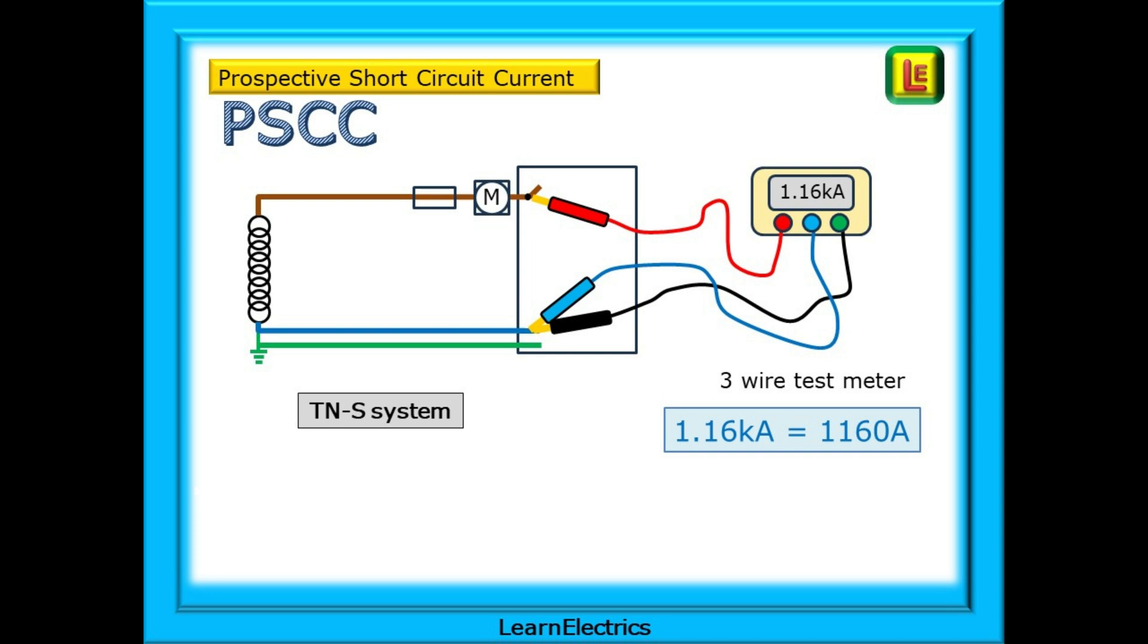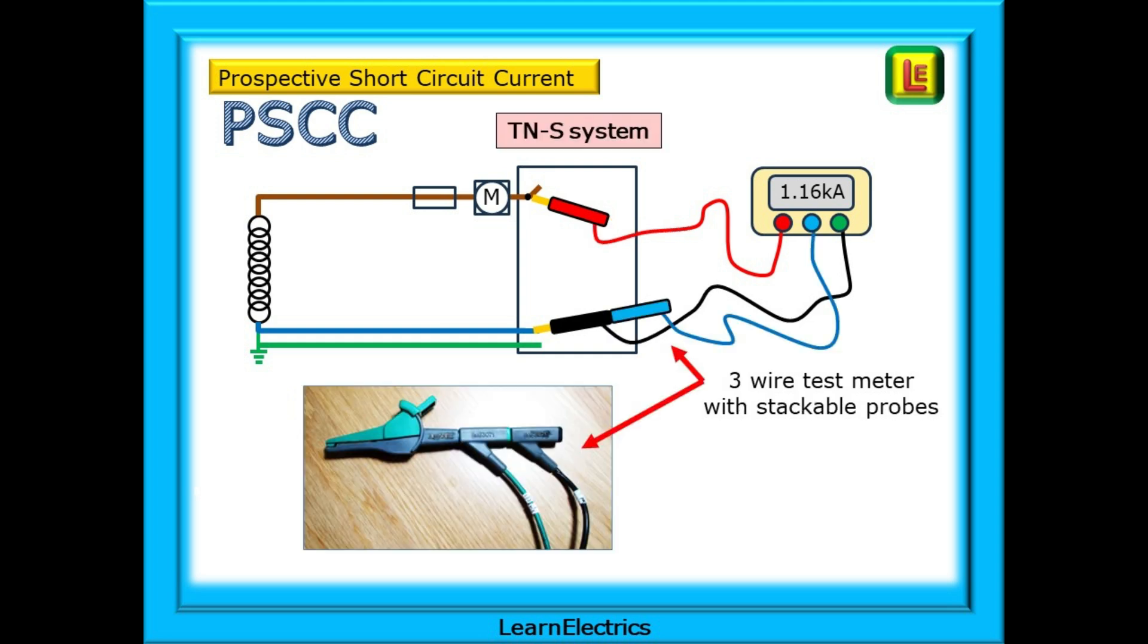It's exactly the same test lead and meter setup as the PFC tests. Nothing is different. The same settings of your test meter dials and positions of the test leads are used for PSCC. And the two wire test can be carried out if your meter does this. If your meter can only do three wire testing it can be useful to have stackable test leads. The probes will plug into each other as shown, making testing much easier and less of a juggling act. Stackable probes can be expensive but I find their ease of use outweighs the initial cost.